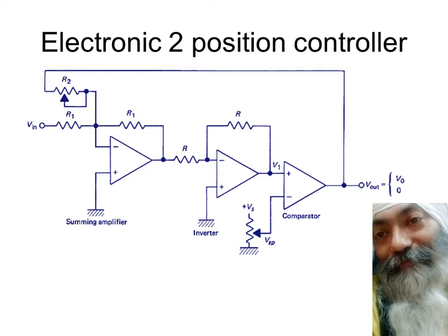And after having reached 24 and it turns off, while the temperature rises again at 25 degree Celsius, it was initially off, it remains off. It means that in this neutral zone it remains in the last state. If it was on it remains on, if it was off it remains off. And this neutral zone is given some, this is called a band. It is also called dead band. This band in this case is of 2 degree Celsius for example. This is given so that we don't have to turn the AC on and off.